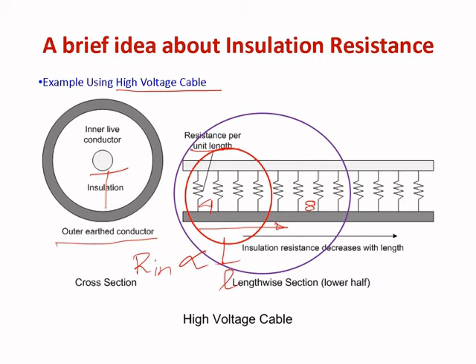The variation of insulation resistance, IR, basically represents insulation resistance with temperature. Generally, the insulation resistance of a dielectric is normally governed by the volume resistivity of the material. The variation of insulation resistance with temperature can be expressed by this formula: R_T2 equals R_T1 divided by A to the power T2 minus T1. What is R_T2? R_T2 is the insulation resistance at temperature T2. R_T1 is the insulation resistance at temperature T1, and A, known as a constant, is an intrinsic property of the dielectric.